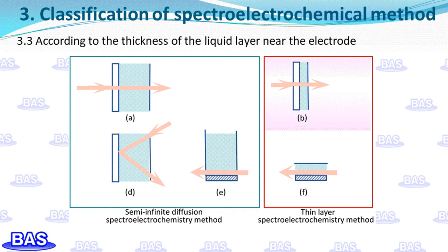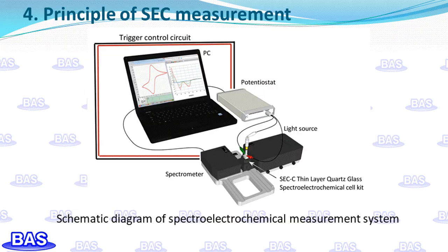In this series, the basic principles of transmission thin-layer spectro-electrochemistry and their applications in electrochemical analysis will be introduced. The overall schematic diagram of a typical spectro-electrochemical measurement system uses transmitting electrodes. The basic measurement system requires a spectrometer, light source, transmissive electrolysis cell, potentiostat, and computer. A circuit that can trigger and control synchronized spectro-electrochemical measurement is also needed. For simple transmission experiments, a standard laboratory spectrometer can usually be used, though electrode connections, laboratory space, and system installation difficulty should all be considered.